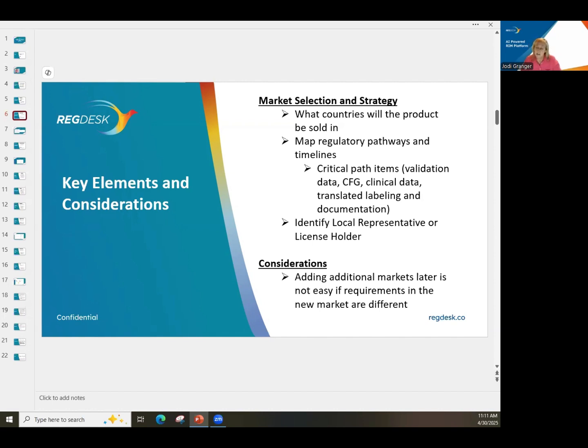So for each of these markets that you intend to sell your product in, it's very important to understand what that critical path item is. The timing that you're going to map out is contingent upon that. If you have a delay in US approval so that it delays when you can obtain a CFG, then that's going to impact all the markets that require that document. So having those interdependencies clearly mapped out, and documenting for each country what you've selected as the critical path item, is really important.